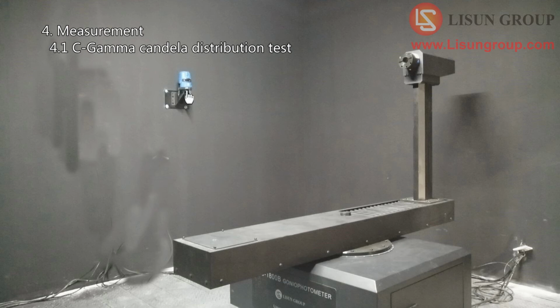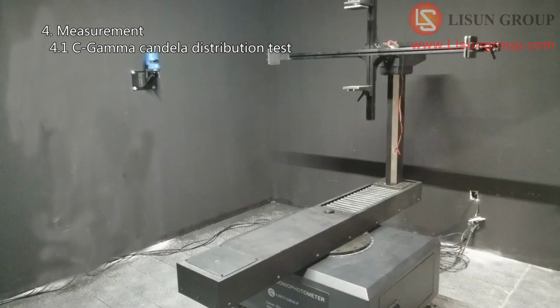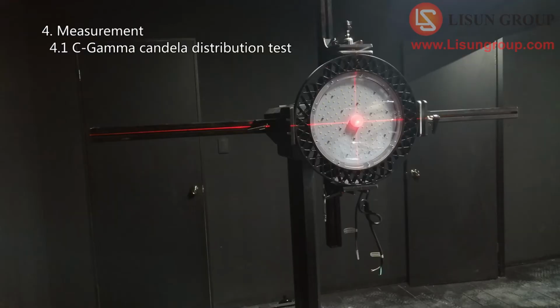Turn on the cross laser and make sure that the laser hits the correct direction. Install the clamp on the main arm of the goniophotometer. Choose Illuminometer for near field. Rotate the gamma angle 90 degrees clockwise or counterclockwise according to the actual situation. Make sure that the cross laser faces the clamp.